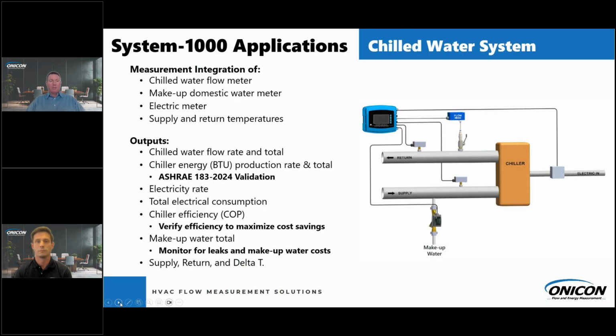So in a chilled water energy system with the System 1000, you'll have a chilled water flow meter. We can add in a makeup domestic water meter. We can add in an electric meter there on the right of the diagram, and we'll have our supply and return temperatures. So far, we've only used one channel of our System 1000. Out of that, we're going to get our chilled water flow rate and total. We'll get our chiller energy BTU production as a rate and total.